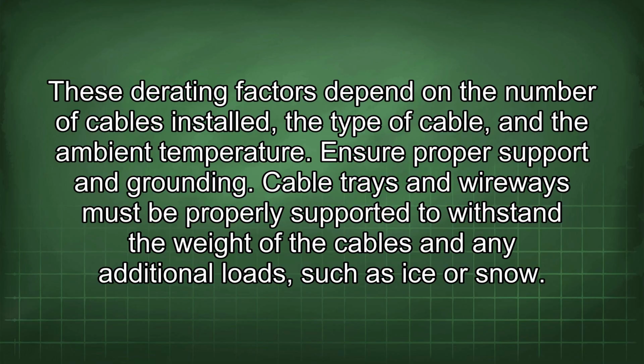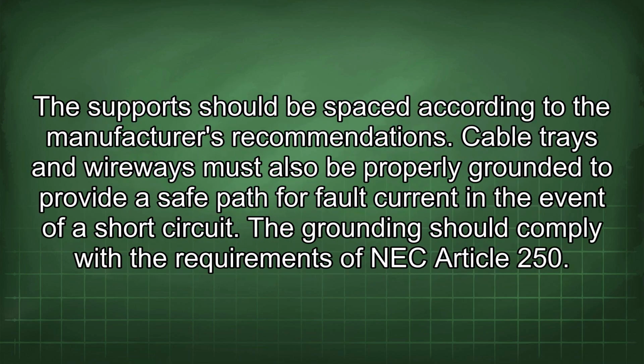Ensure proper support and grounding. Cable trays and wireways must be properly supported to withstand the weight of the cables and any additional loads such as ice or snow. The support should be spaced according to the manufacturer's recommendations.